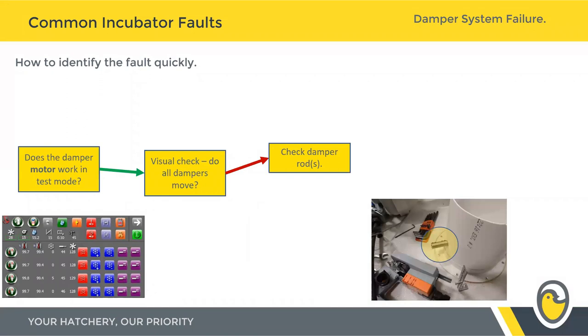If the damper does work, check each individual damper to make sure all the connecting rods are transitioning that power all the way down the length of the machine. If it doesn't work, check those damper rods and connections to make sure those grub screws are nice and tight. Note that on the coupling there are four grub screws — two for each damper rod — so even if one comes loose, the other should keep it secure. When tightening and installing, put a small amount of Loctite on those threads to keep them secure.